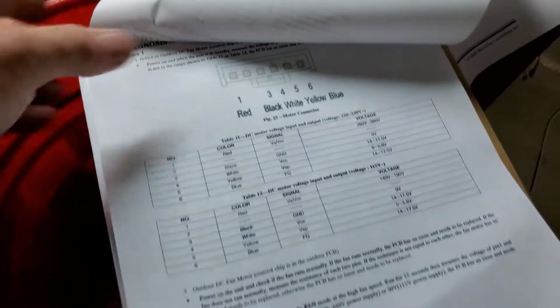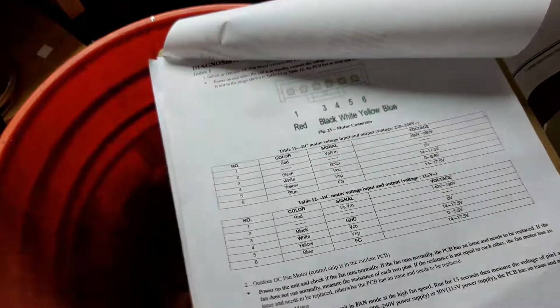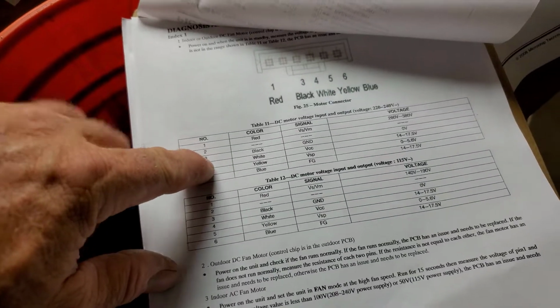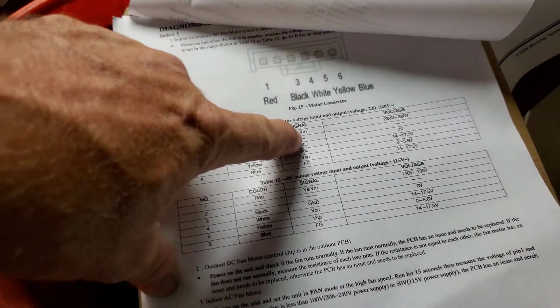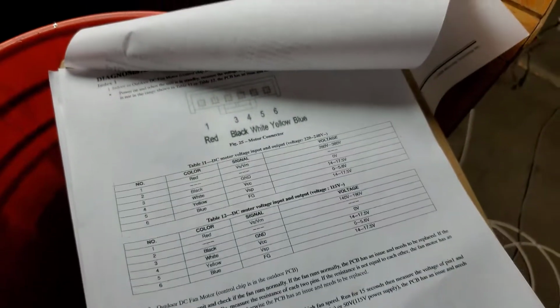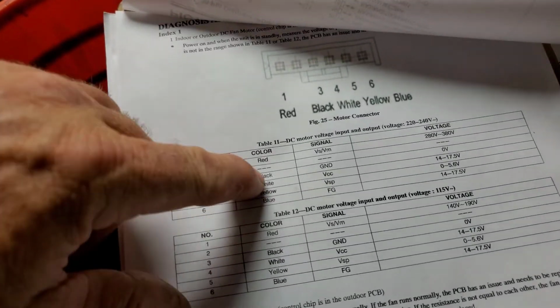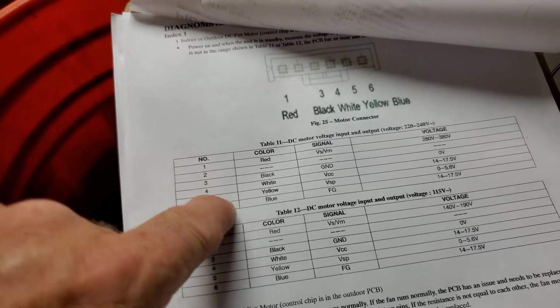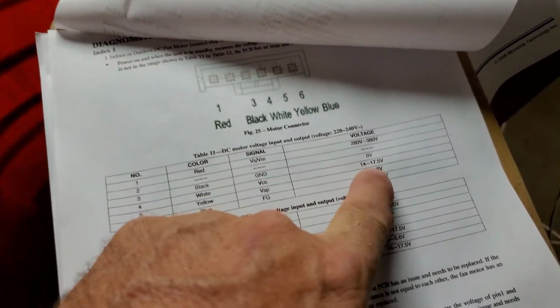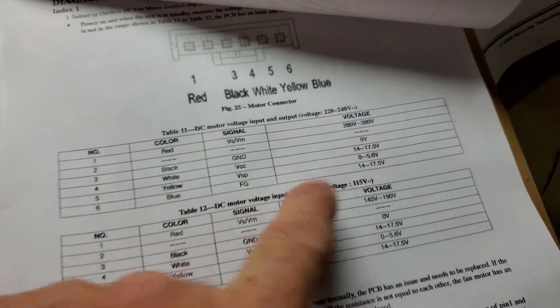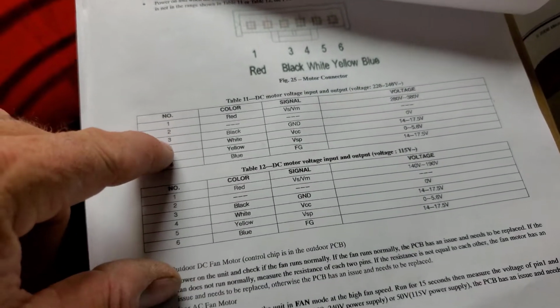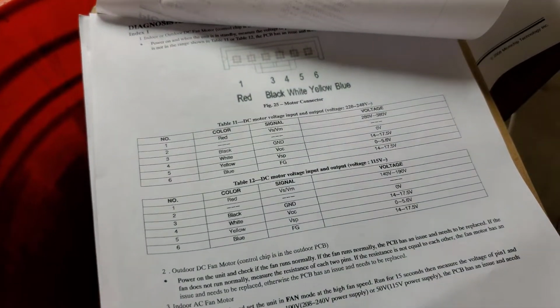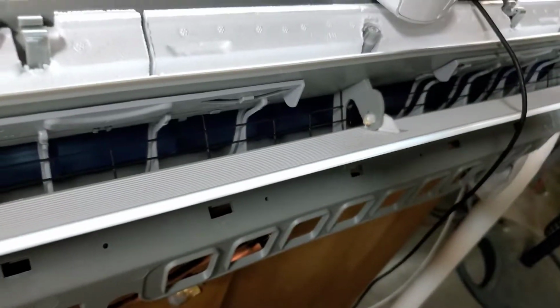This plug is the blower motor. And I believe all the outdoor fan motors and stuff of this same nature work the same. Between three, which is ground, and one, which is 300 volts. And then between three and four, you put about 15 to 17 volts, just exactly what it says. And between three and five, it's your signal in, 0 to 5 volts, 5 volts max on the dial, which you can hear.